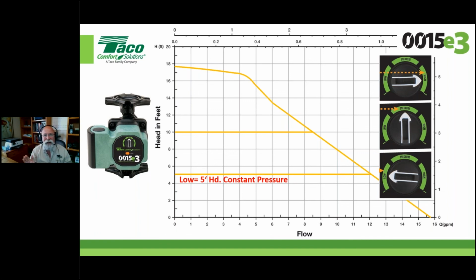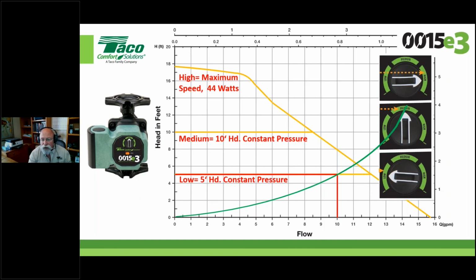But it's very slight. Okay, think of it this way: there are no zone valves or thermostats or actuators or anything that are going to change the hydraulics that this pump is ever going to see in a primary boiler circ application. Hopefully that rings true to everybody and you understand where I'm going with that. There's the medium head and there's maximum head. In this case, we knew we were at 10 at 5, and that's what you're going to see pretty much. It might move a little bit back and forth here depending on temperature, viscosity, and some other things, or how well you did your estimate. But the beauty is I can come back this way as well. Okay, it'll just find its happy spot somewhere along this line.